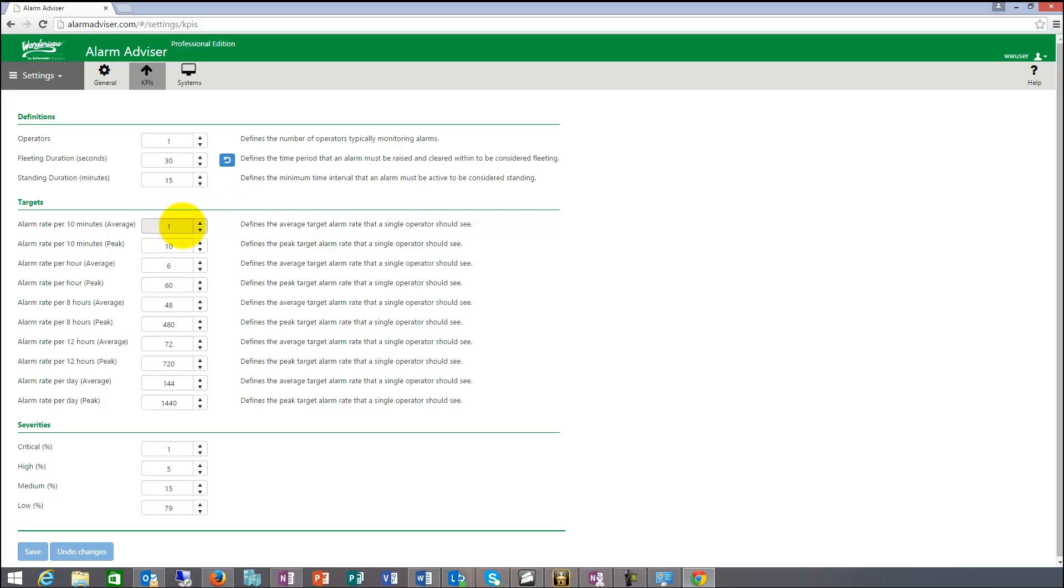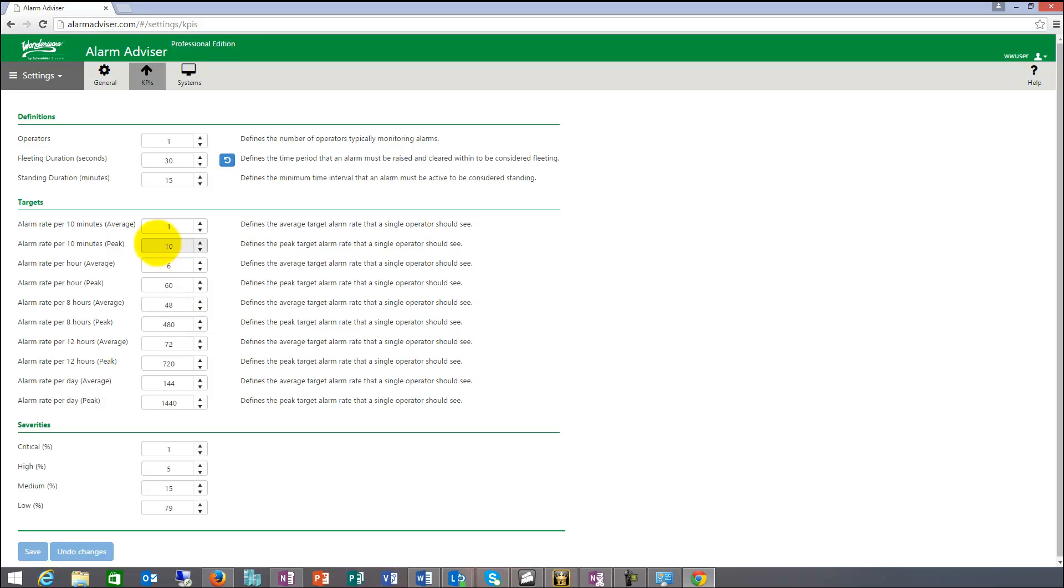So here's the alarm rate that we talked about that are part of the EEMUA: 1 per 10 minutes, 6 per hour, 60 per hour peak, 48 per 8 hours average. So I can make changes to this if I want to and that gets reflected into the dashboard metrics.